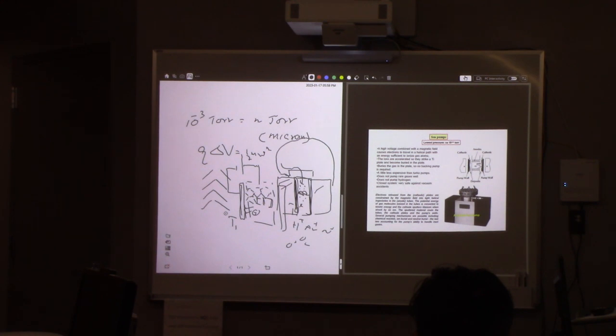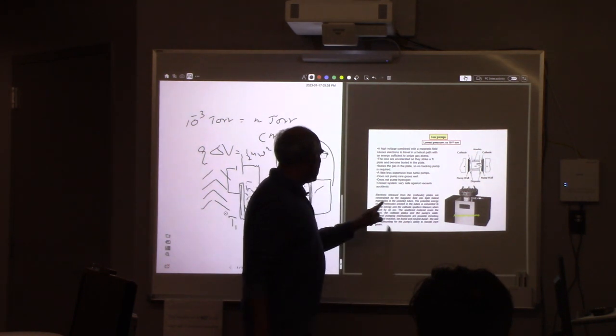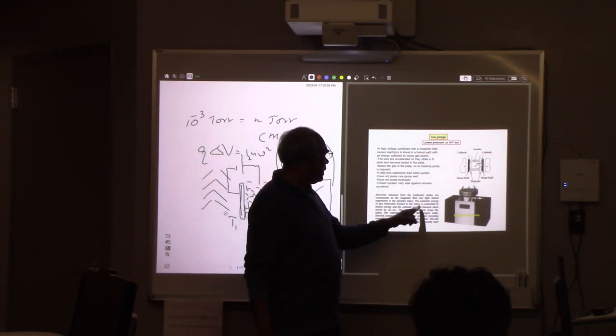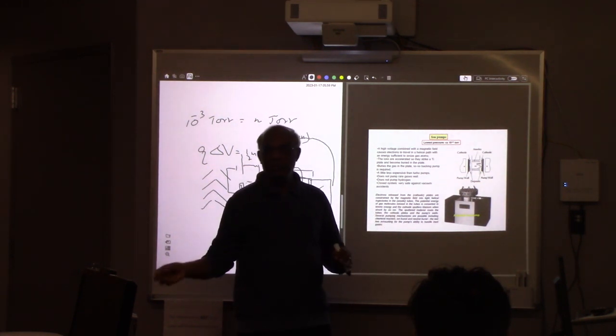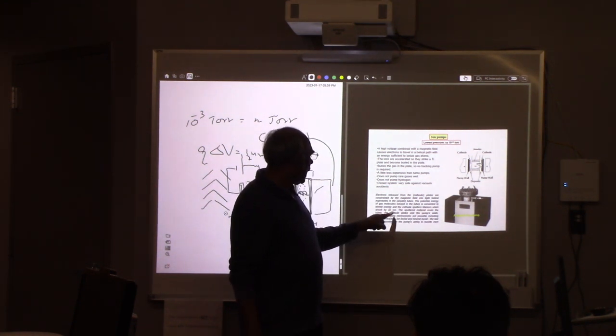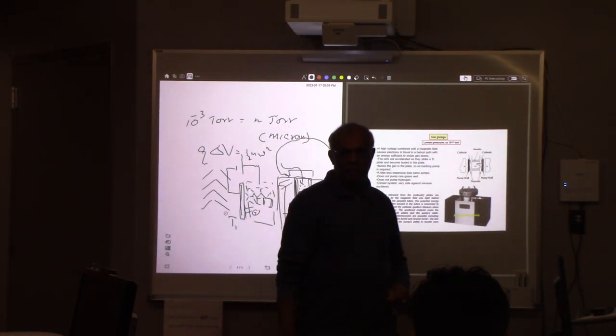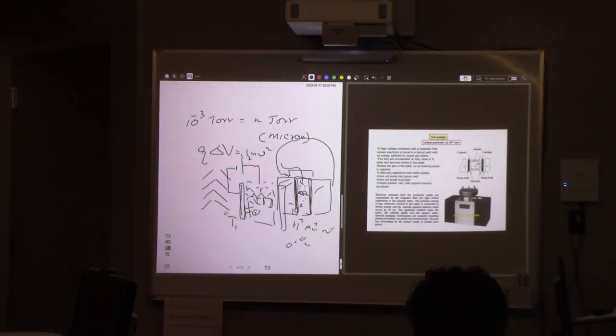So that's basically what getters means - you'll see that word. Electrons released from the cathode plates are constrained by the magnetic field into these helical trajectories. The potential energy of the gas molecule ionized in the tube is converted to kinetic energy, and the cathode sputters titanium when struck by the ion - that's what sputtering means, it just removes material. The sputtered material coats the tubes, the cathode plates, and the pump's walls. That's basically the idea, you get it, right?